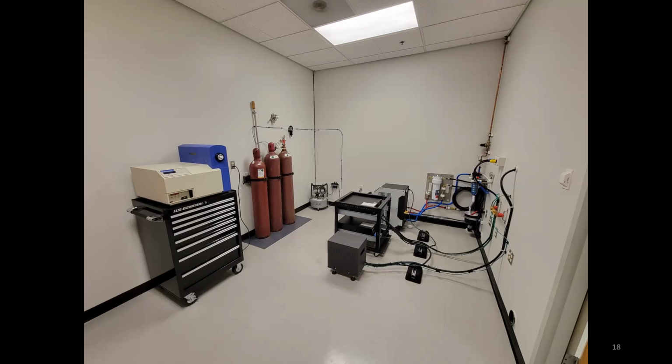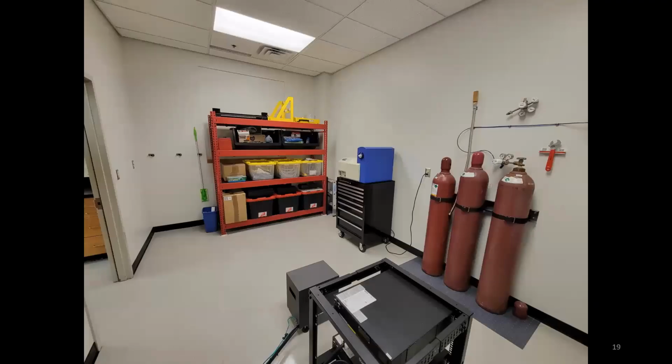It operates at a fairly high vacuum, kind of 0.1, less than a millitorr kind of thing. So yeah, hopefully it works. We haven't been able to try it out yet because we don't have the gases. And if we were to turn it on and try to do it without the gases, we could burn it up. So it's kind of a problem.